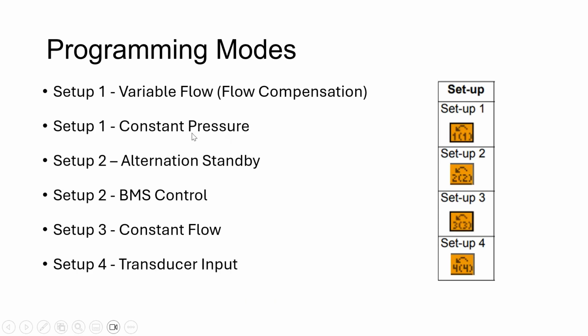Constant pressure, and I'm going to show you another screen about that. That's setup two. Also setup one, but a different part of that screen. Alternation standby is setup two. BMS control is also setup two. Constant flow, that's probably the second most used, or maybe the transducer input one is, believe it or not. But constant flow would be setup screen 3, and that's maybe for a primary system.